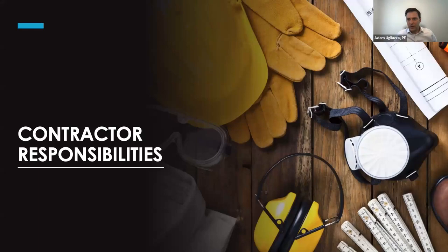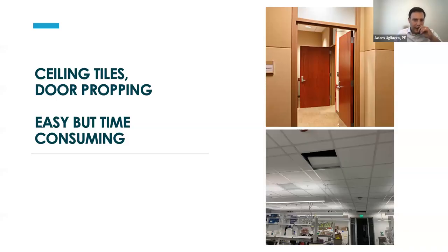As I mentioned, this is the time consuming prep that I'd mentioned. So, ceiling tile. If you have lay-in ceilings, the whole goal is to get equal pressure across all the boundaries of the building, that six-sided box. Lay-in ceilings can block certain portions of the roof if it's on the top floor, or the exterior wall if it's along the perimeter. So we generally recommend, and a lot of the standards say, one per 500 square feet or one per room. Sometimes that can be tough to do. You're going to have to have a ladder and go into each room, so it's very time consuming. It's easy to do, but it just takes a while.